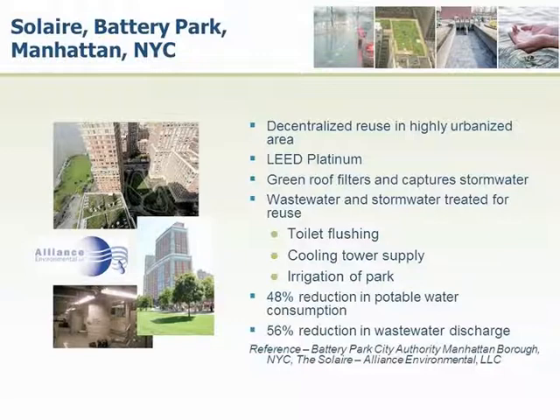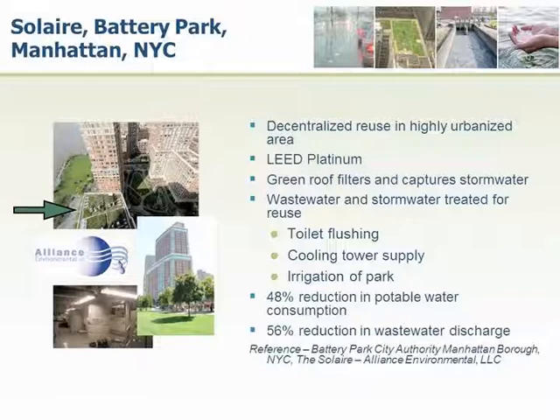A highly urban example: a mixed-use development in Battery Park, Manhattan — one of about a dozen similar building-scale systems in the Battery Park redevelopment, all using membrane bioreactor (MBR) systems. The MBR is built into the basement of the facility, and they also have a green roof for stormwater harvesting. Reclaimed water uses include toilet flushing, HVAC cooling, outdoor irrigation, and in some of the newer Battery Park systems, laundry.